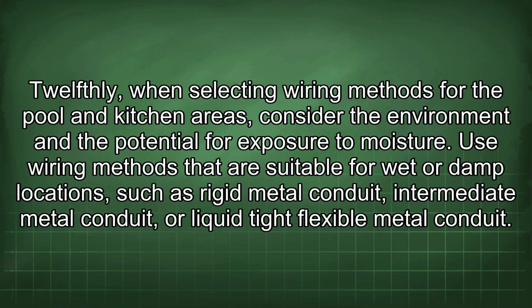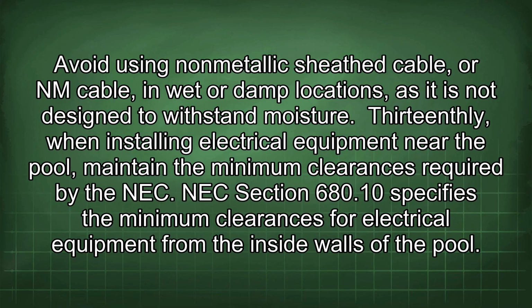12thly, when selecting wiring methods for the pool and kitchen areas, consider the environment and the potential for exposure to moisture. Use wiring methods that are suitable for wet or damp locations, such as rigid metal conduit, intermediate metal conduit, or liquid-tight flexible metal conduit. Avoid using non-metallic sheath cable or NM cable in wet or damp locations, as it is not designed to withstand moisture.